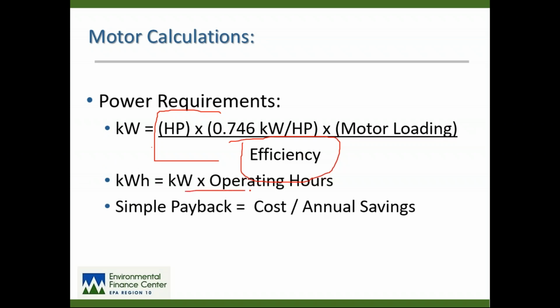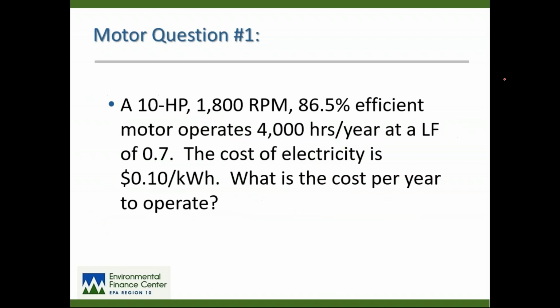The other factor is operating hours, which is just kilowatt hours equals kilowatts times hours, and the simple payback. Remember, this is what we're trying to arrive at. When will this new piece of equipment be paid back in energy savings? And that's the upfront cost of the equipment divided by the annual savings in energy.